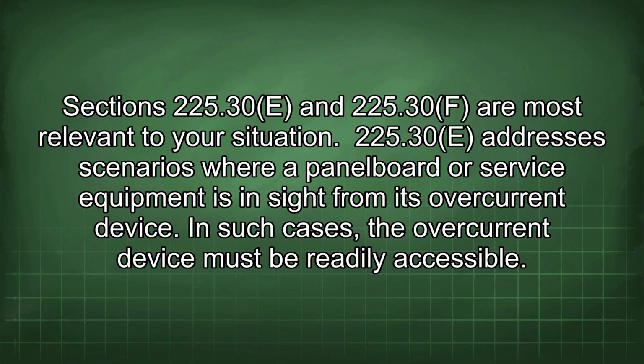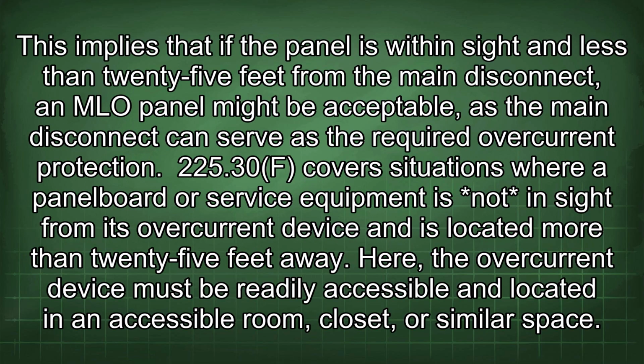225.30e addresses scenarios where a panel board or service equipment is in sight from its overcurrent device. In such cases, the overcurrent device must be readily accessible. This implies that if the panel is within sight and less than 25 feet from the main disconnect, an MLO panel might be acceptable, as the main disconnect can serve as the required overcurrent protection.